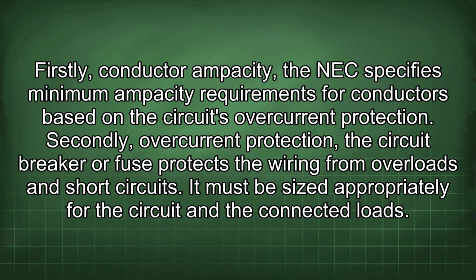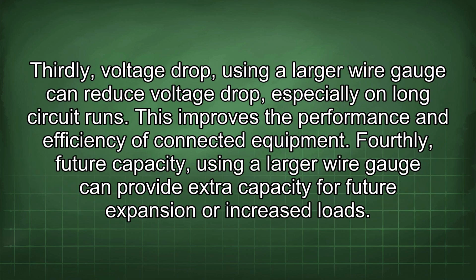hazards. Firstly, conductor ampacity. The NEC specifies minimum ampacity requirements for conductors based on the circuit's overcurrent protection. Secondly, overcurrent protection. The circuit breaker or fuse protects the wiring from overloads and short circuits. It must be sized appropriately for the circuit and the connected loads. Thirdly, voltage drop. Using a larger wire gauge can reduce voltage drop, especially on long circuit runs. This improves the performance and efficiency of connected equipment.